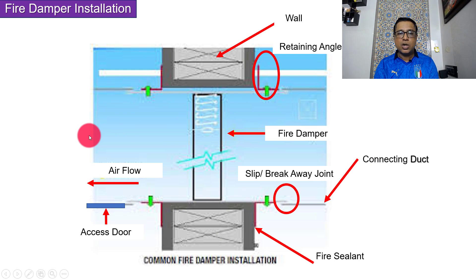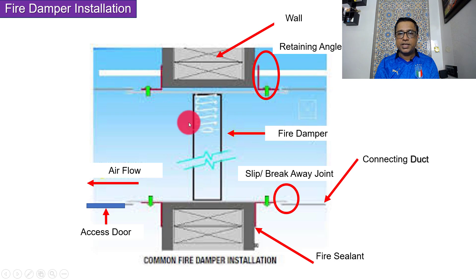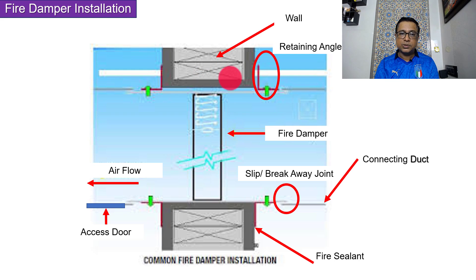In case of fire, the damper should act as a perfect wall — avoiding fire coming from one zone to the other. These are fusible link fire dampers. There are two types of heads: either you take the entire assembly inside the fire damper, checking the duct size as it impacts velocities, or you can keep the head outside the fire damper. These dampers are supplied with sleeves.